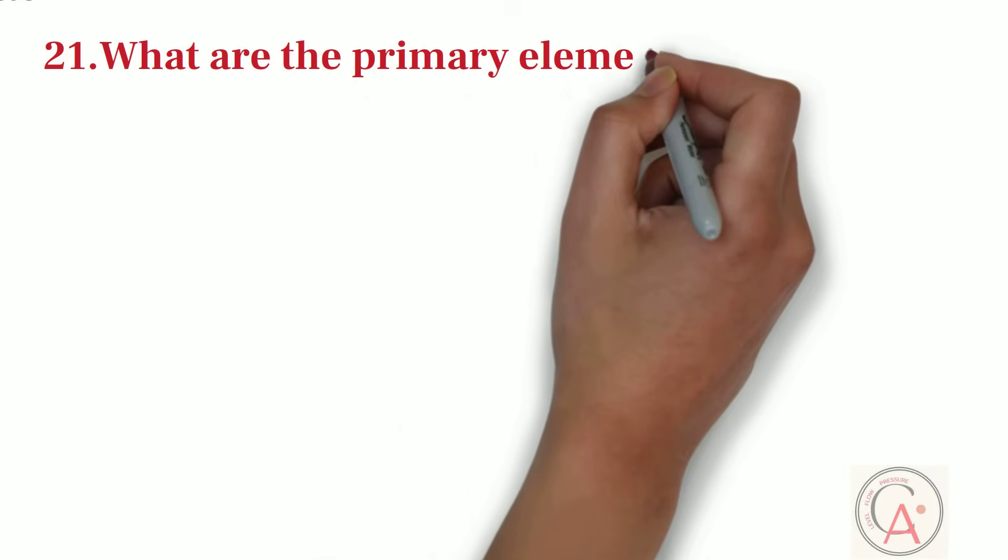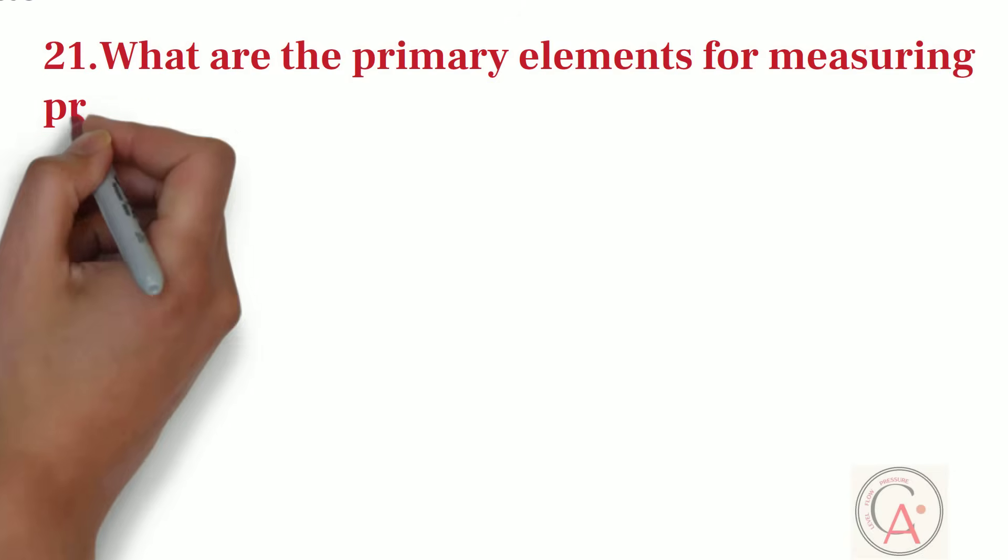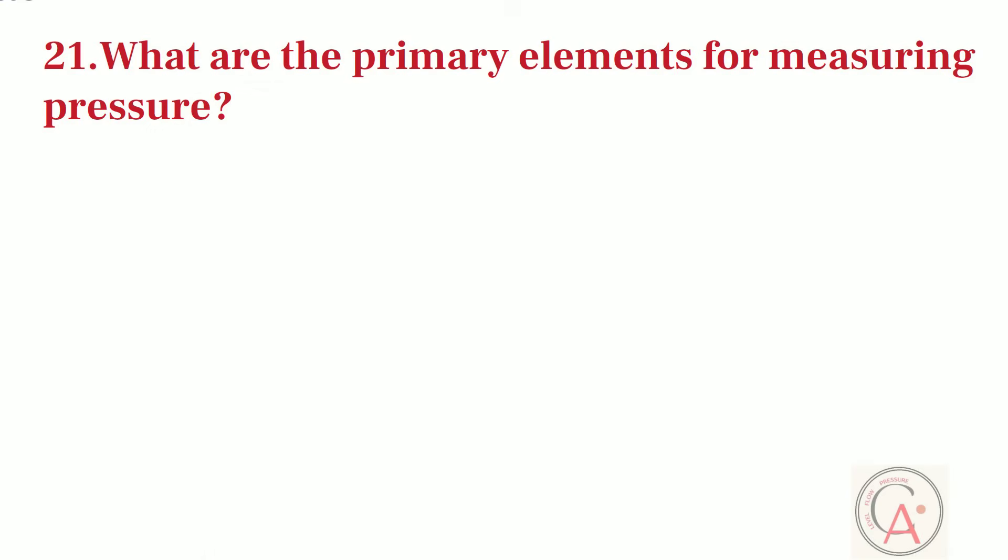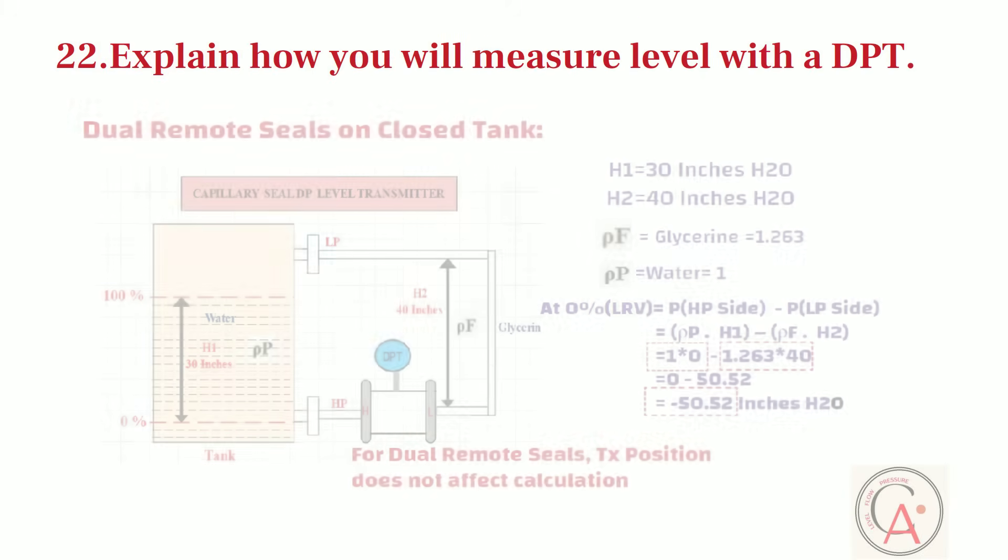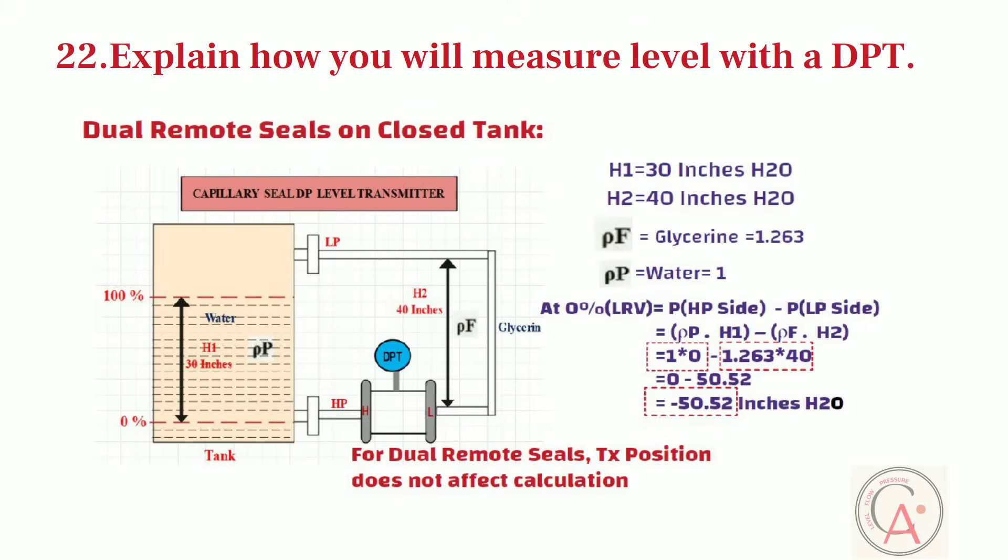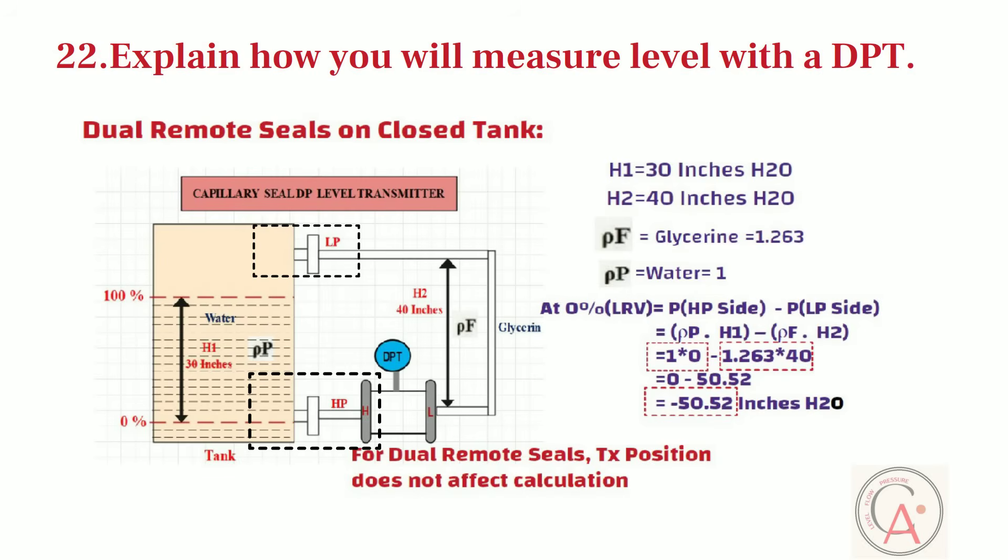Next question is, what are the primary elements used for measuring pressure? The primary elements used for measuring pressure are Bourdon tube, Diaphragm, Capsule, Bellows, Pressure springs. Next question is, explain how you will measure level with a differential pressure transmitter. To measure level with DPT, the bottom connection of the vessel is connected to high-pressure side of the transmitter, and top connection of vessel is connected to low-pressure side of DPT.